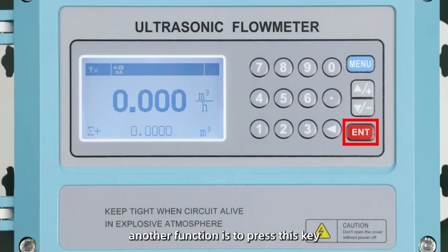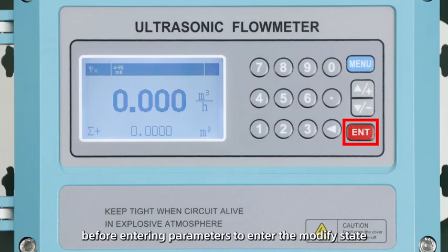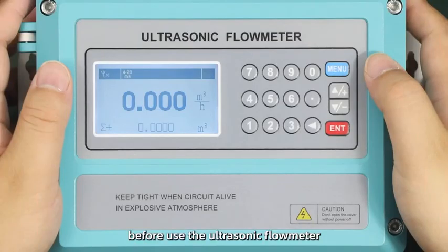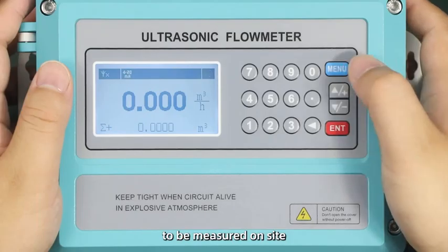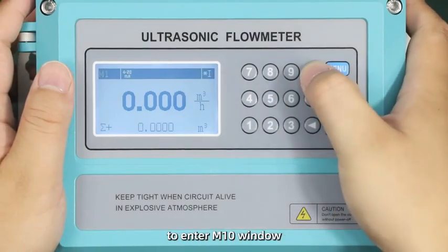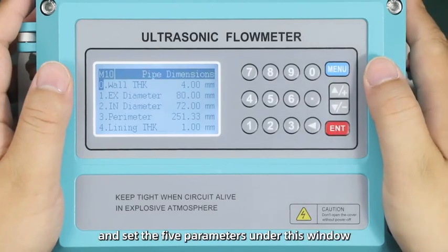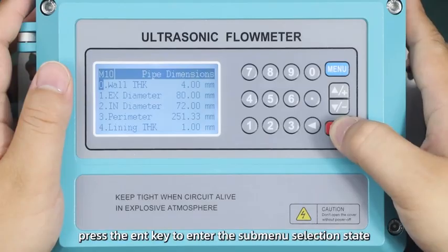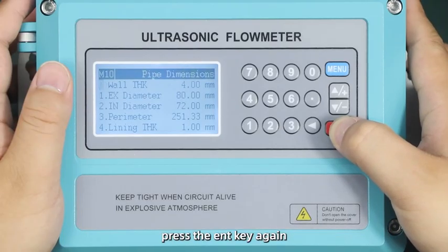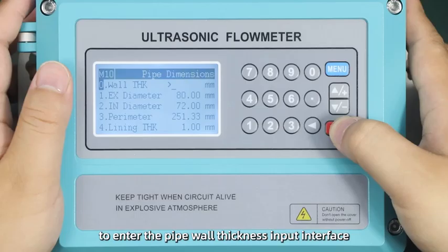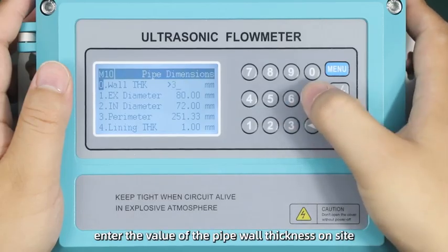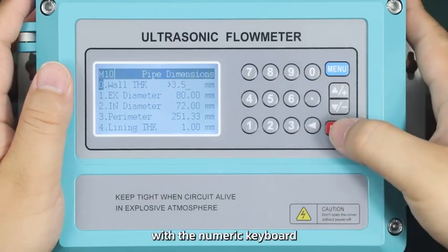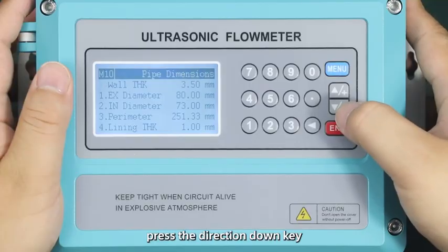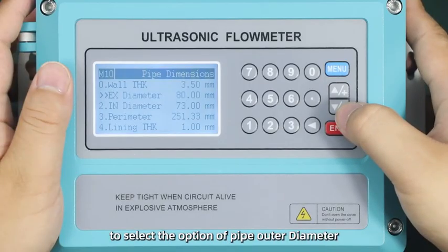Another function is to press this key before entering parameters to enter the modify state. Before use, the ultrasonic Flowmeter needs to accurately set the specific parameters of the pipeline to be measured on site. Press the menu key and enter 1 and 0 to enter M10 window, and set the 5 parameters under this window. Press the ENT key to enter the submenu selection state. Select the pipe wall thickness option. Press the ENT key again to enter the pipe wall thickness input interface. Directly enter the value of the pipe wall thickness on site with the numeric keyboard, and press the ENT key to confirm. Press the direction down key to select the option of pipe outer diameter.